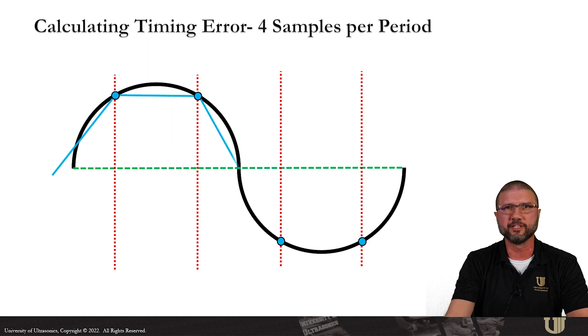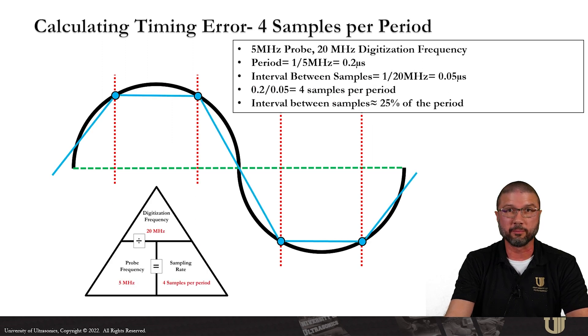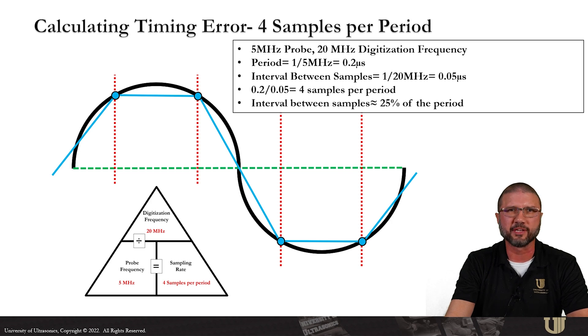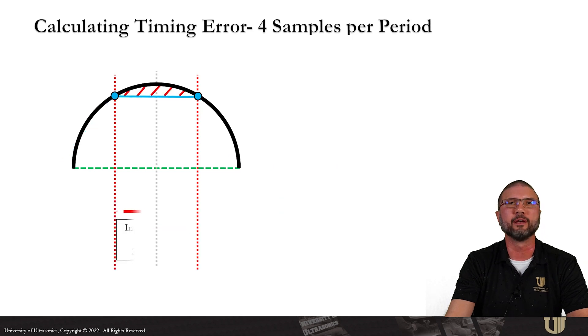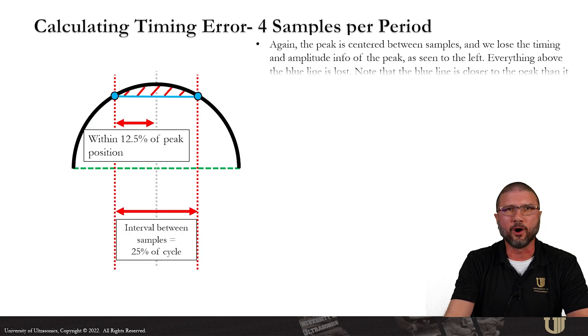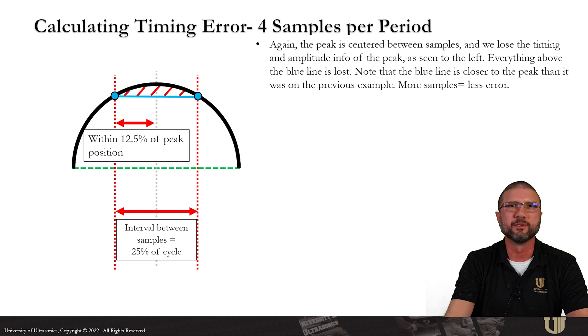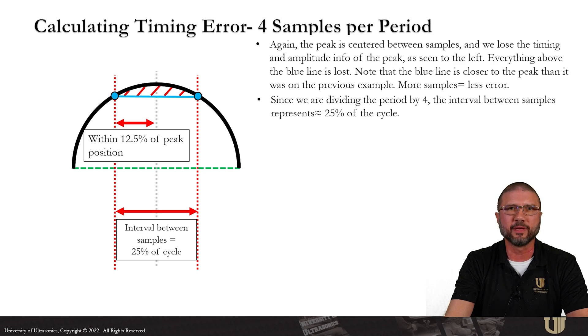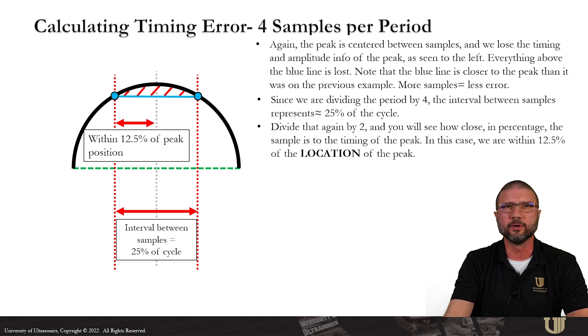For the next scenario: a 5 megahertz probe with a 20 megahertz digitizing frequency, giving us four samples per period. Notice that none of the samples actually aligned with the peaks — where a sample lines up on a cycle is random and impossible to predict. There's no guarantee you'll ever find the actual peak of the signal, but the closer we get, the better. The max error always occurs when the peak is centered between samples. Note that the blue line in this case is closer to the peak than in previous examples — more samples equals less error.